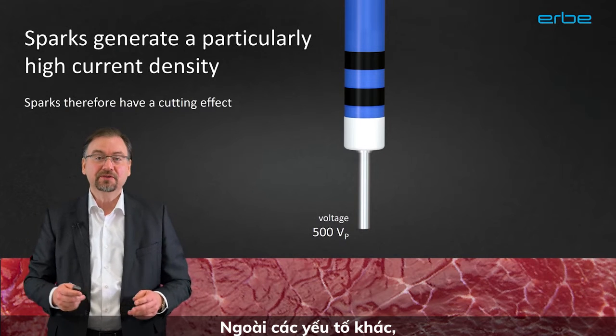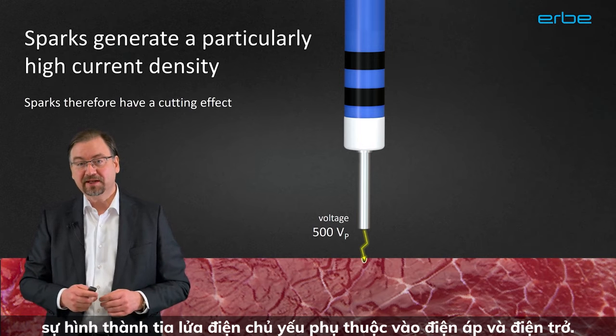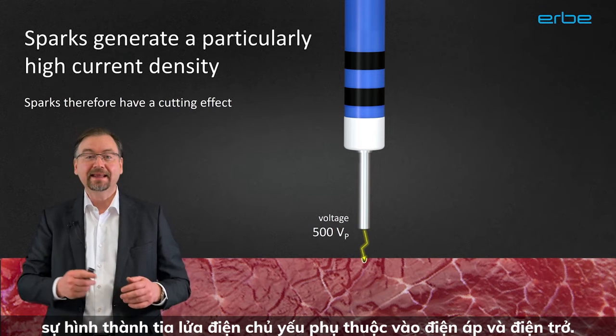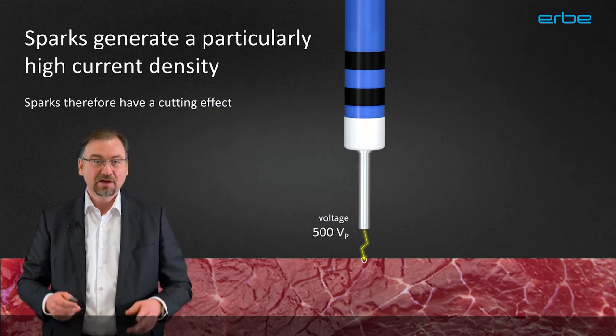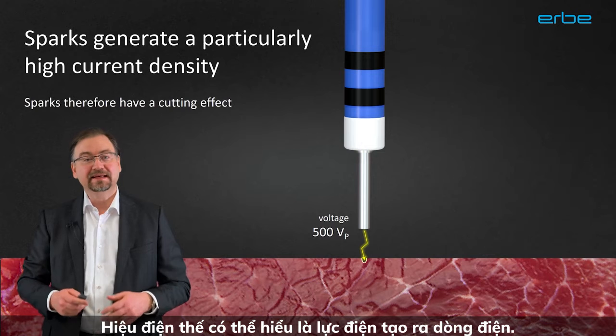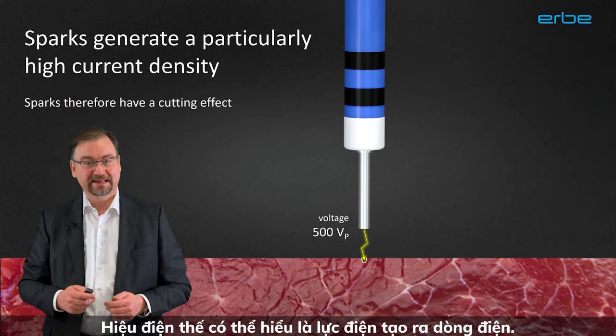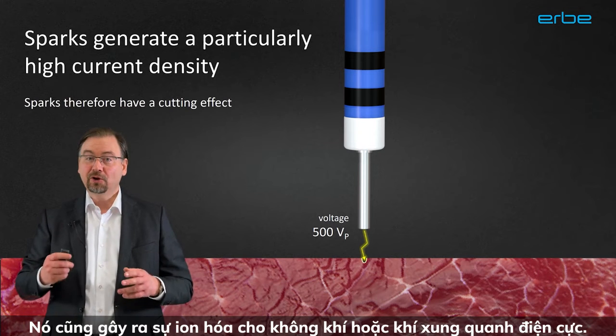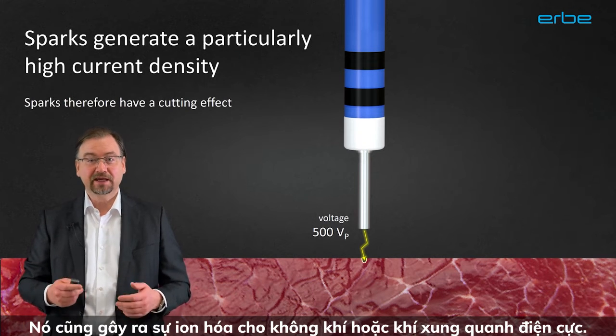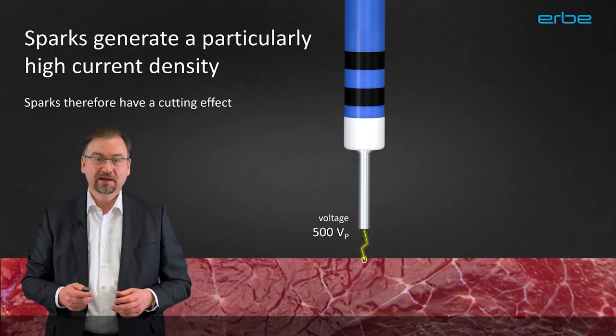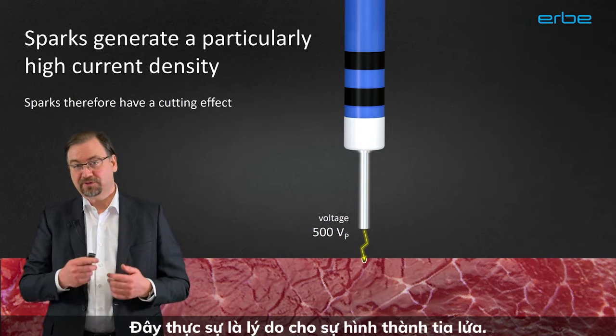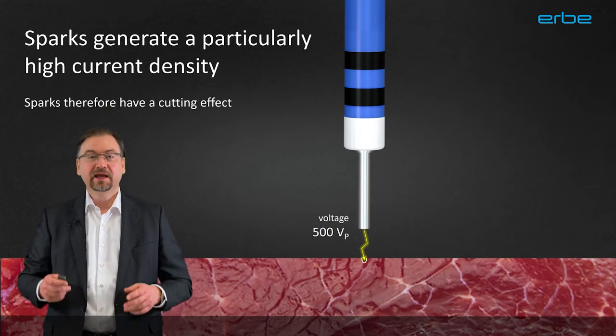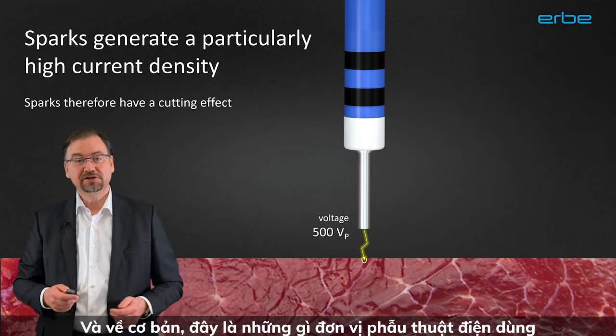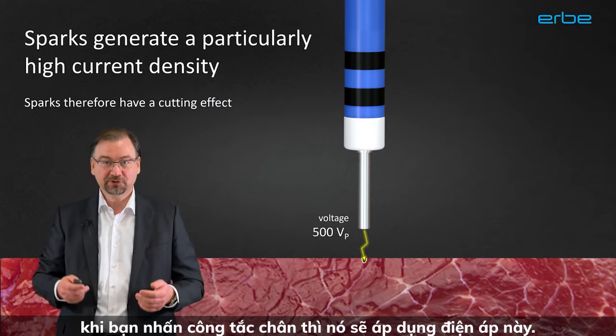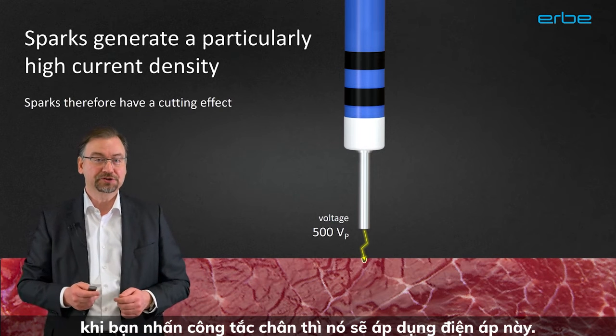Beside other factors, the spark formation mostly depends on the electrical voltage and the electrical resistance. The voltage can be understood as the electric force that generates the electric current. It also causes an ionization of the air or gas around the electrode. This actually is the reason for the spark formation. And this is basically what the electrosurgical unit is for. When you press the foot switch, it will apply this voltage.